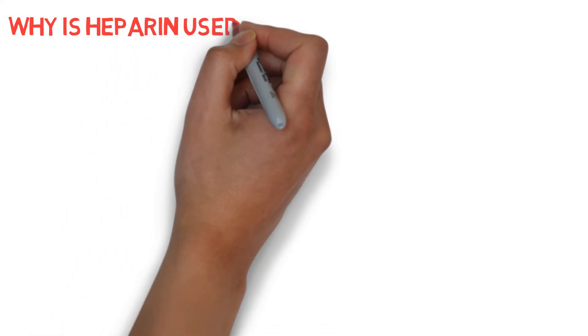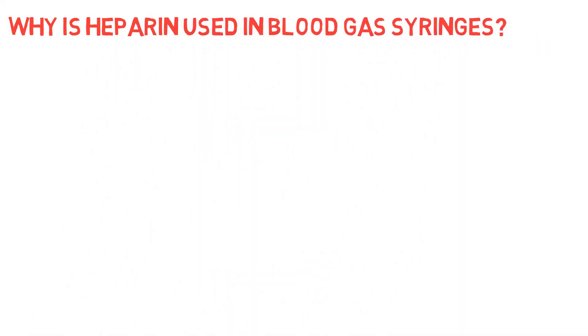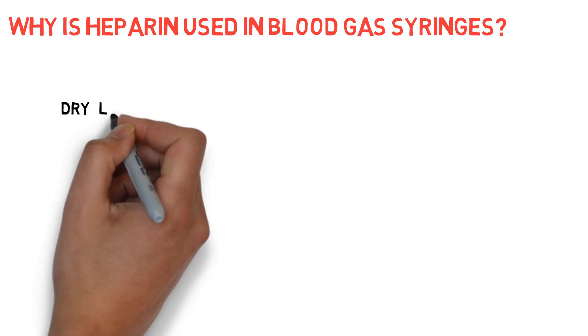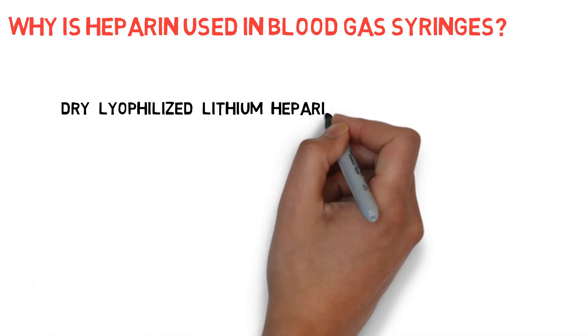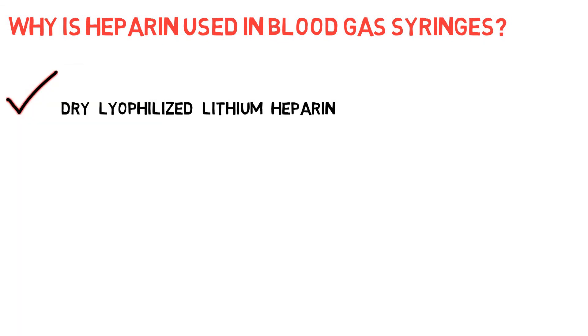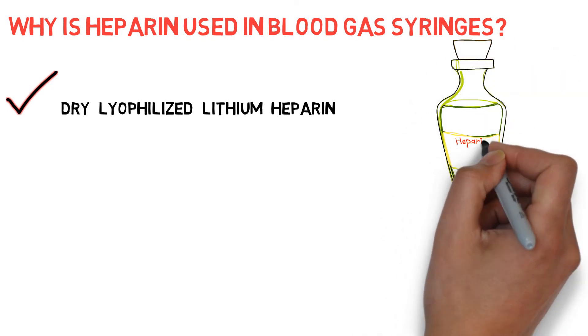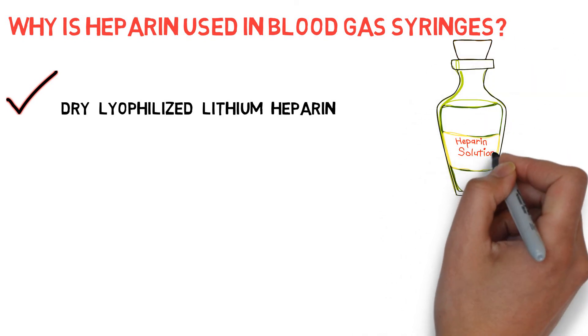Why is heparin used in blood gas syringes? Coagulation of the blood sample must be avoided because clots interfere with the function of the blood gas analyzer. Dry lyophilized lithium heparin is used so that electrolyte measurement can be performed using the blood gas sample. Moreover, dry heparin reduces the risk of pre-analytic errors caused by dilution of the sample with the volume of the liquid form of heparin.